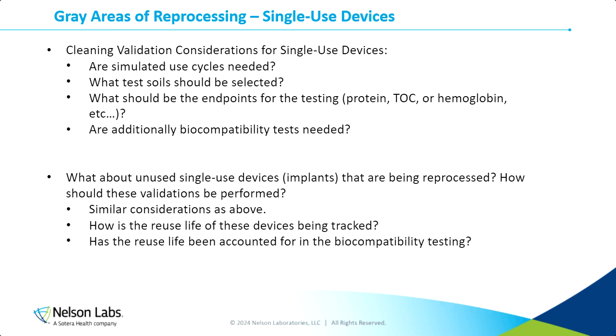You'll want to look into creating a system to track how many times that implant has been reprocessed, and you want to account for that reuse of the implant during the biocompatibility testing as well. There is a draft FDA guidance on unused single-use implants, bone plates and screws specifically, that you can reference. But again, this is just a draft guidance. It's not a published guidance yet, so it's not necessarily one that can be fully referenced.